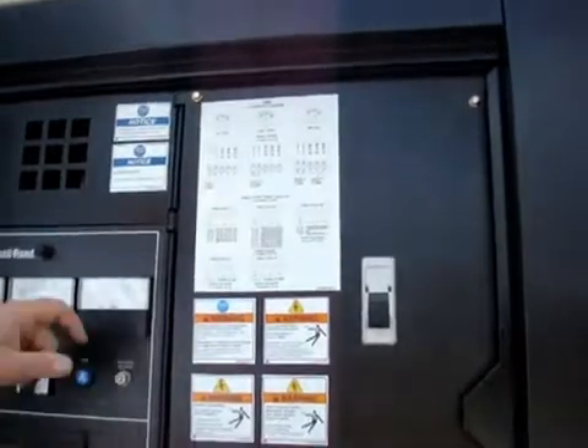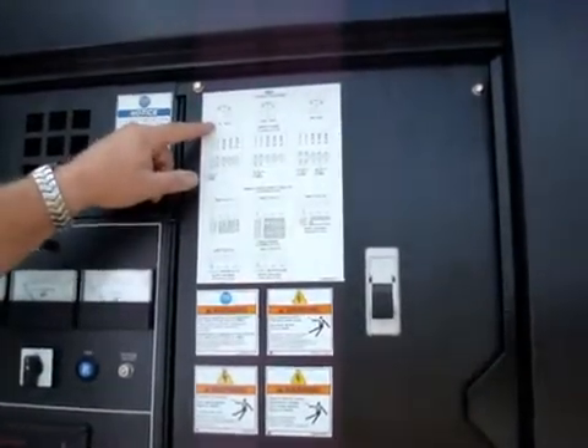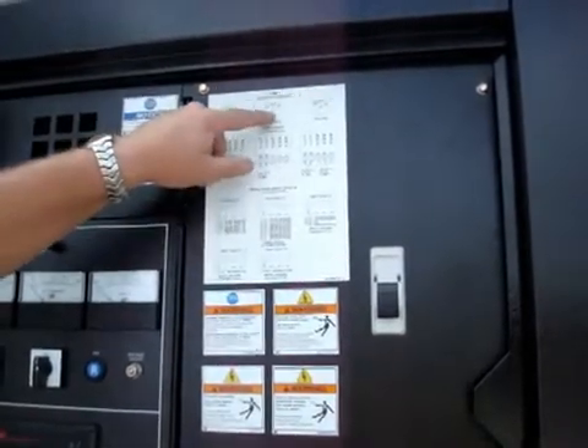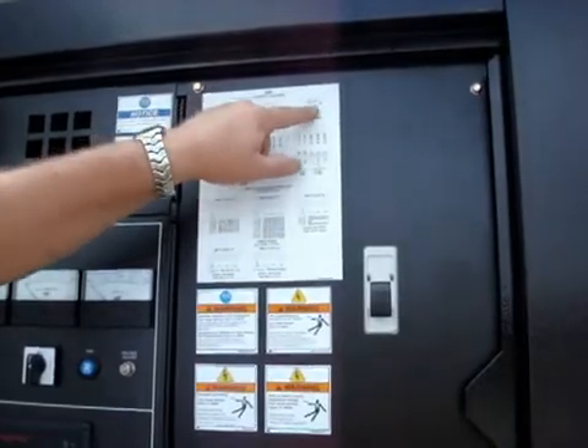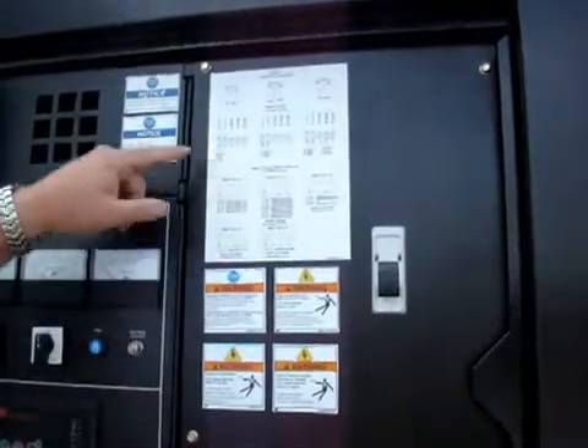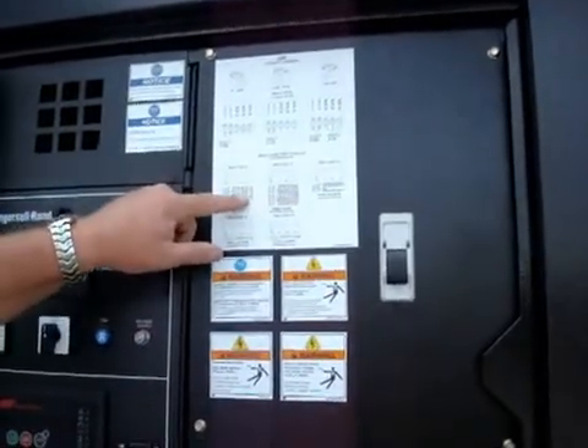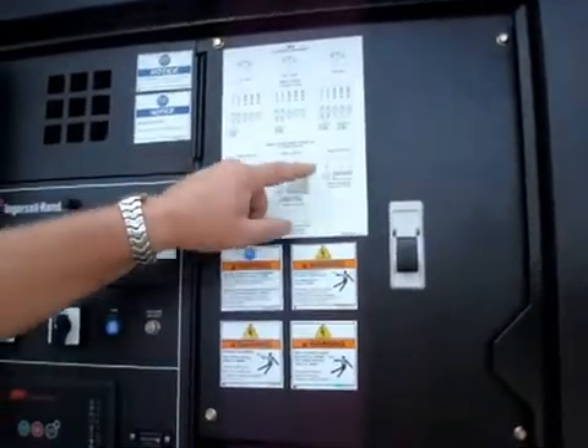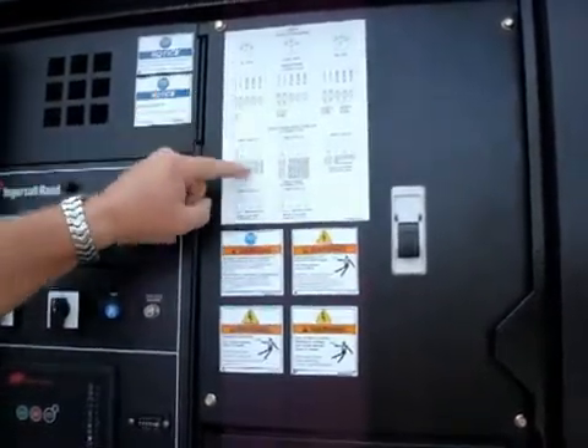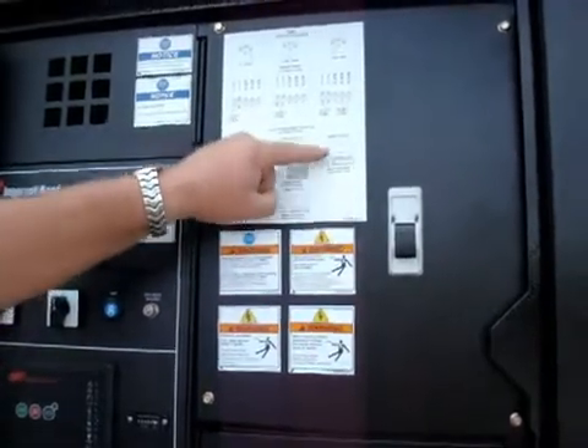Also included with each unit is a capacity diagram. The capacity diagram is set up to show the voltage operations, in this case 480 volts, in this instance 208, 240 3-phase, and this one is 240, 120 single phase. It indicates which receptacles can be used in which voltage mode and gives us our current and kVA limits for each mode. So prior to starting up and running, we will want to refer to this chart to make sure that we're not overloading the machine prior to starting it up.